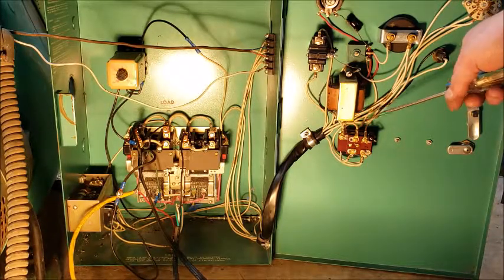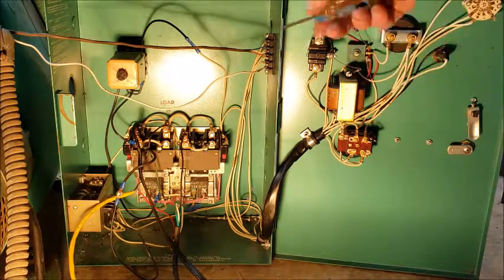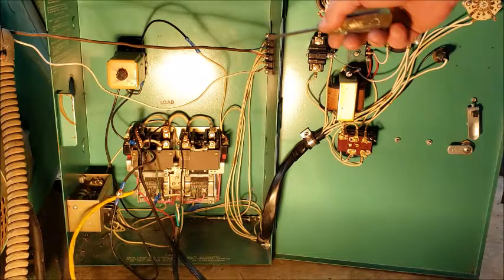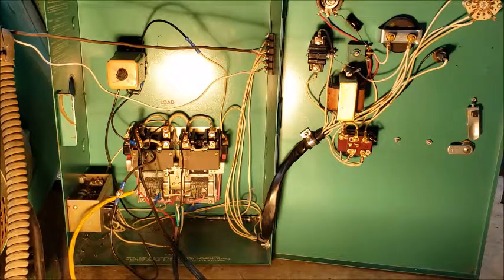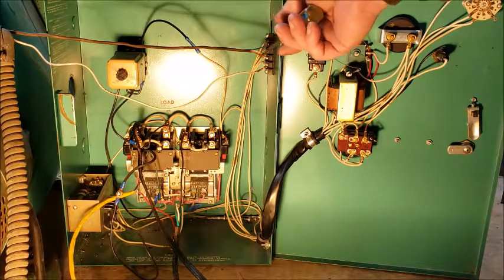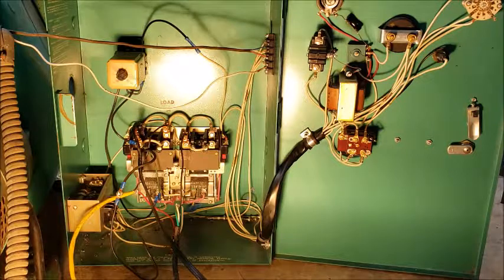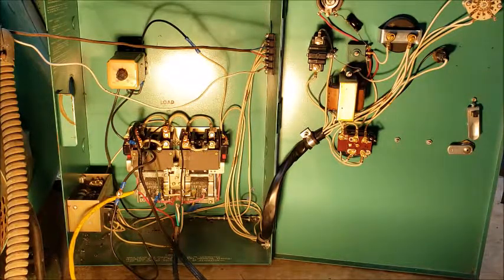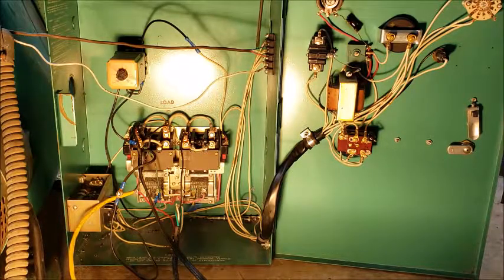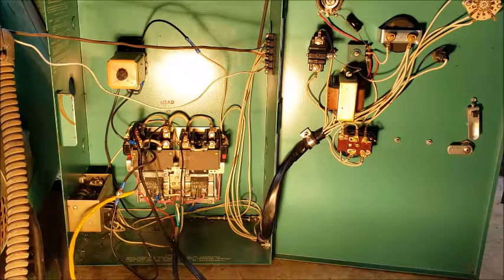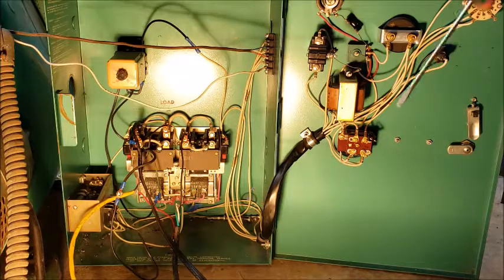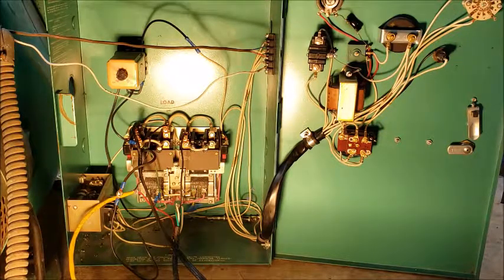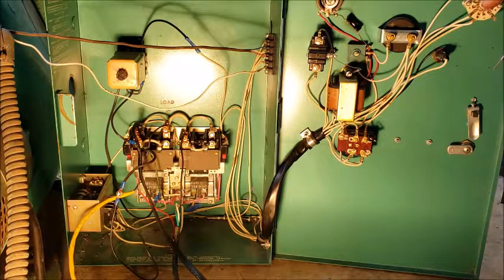And that is grounded to pin number one here on the terminal block which goes back to the generator and that's ground. Terminal 2 on here, the white wire, is the stop circuit. And terminal 3 is the start circuit. And if you ground terminal 3 the engine will crank over. If you ground terminal 2 the engine will stop.